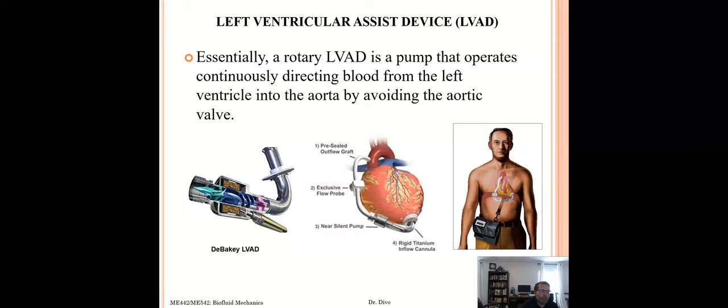The original designs were made as pulsating pumps to be in synchrony with the heart cycle. They were fitted as either a membrane or a pulsatile pump that would have a control system, maybe through a pacemaker, that would allow the pump to pulsate at the same rhythm as the heart. It was believed at the time that if you produce a continuous flow signal, you might damage some of the circulatory system, or the patient might not react the same. But it turns out that's not the case. Further clinical studies over the last 30 years have demonstrated that it's okay for this machine to be a continuous flow pump. Furthermore, continuous flow pumps like this are far more reliable than a pulsatile pump, like a membrane pump that pumps up and down.